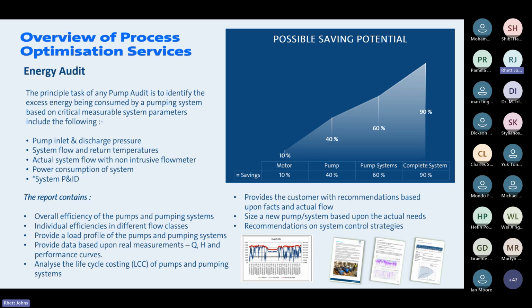And really, when you've got an oversized pump and it's running at a low flow condition, it runs very far left of curve. And very far left of curve is where you get the lowest possible efficiency. So based off of these findings in an audit, you can define the flow states, that is, the best efficiency point where it's running in different flow classes, as well as find out where it spends most of the time operating. And using that methodology, we can then look at resizing your pump system in order to have it running continuously at the best possible efficiency point on a pump.